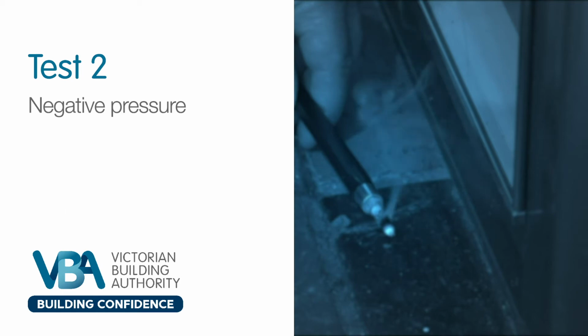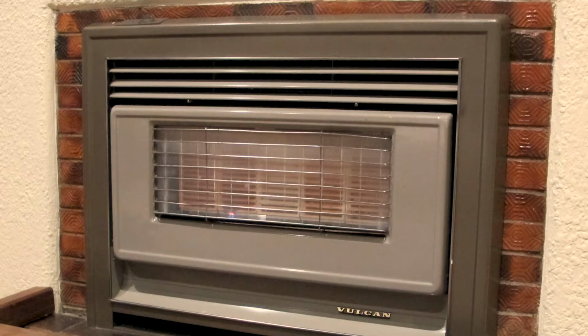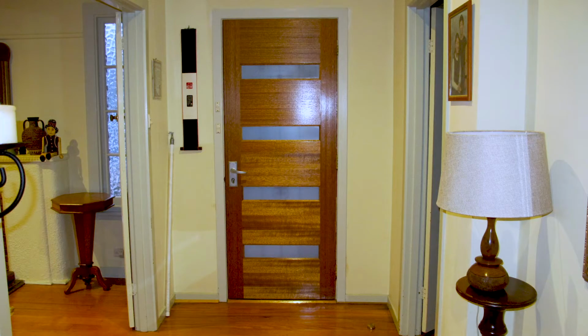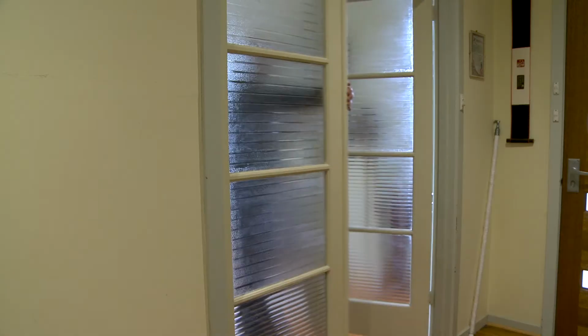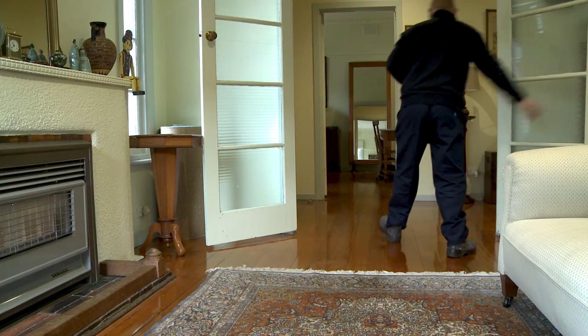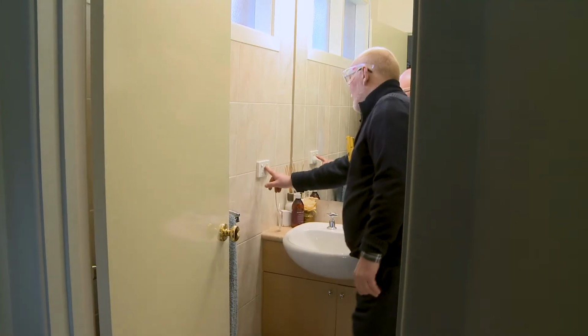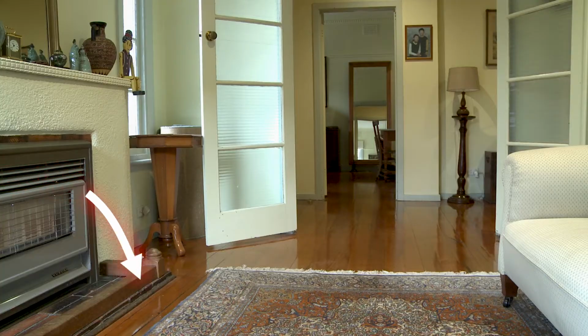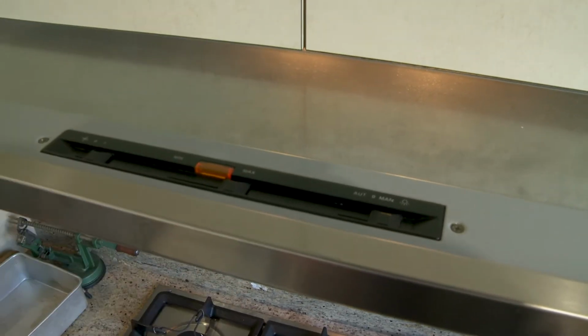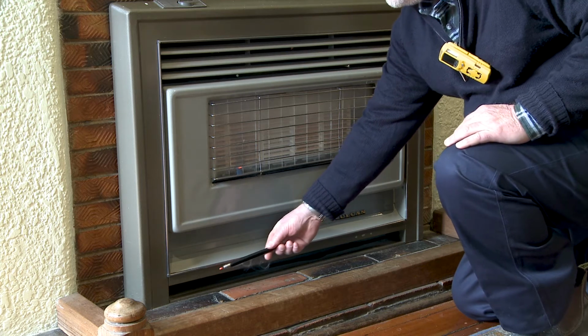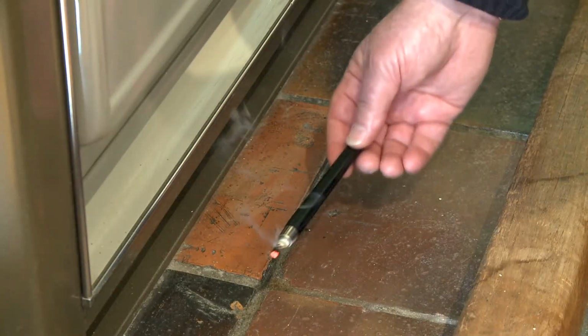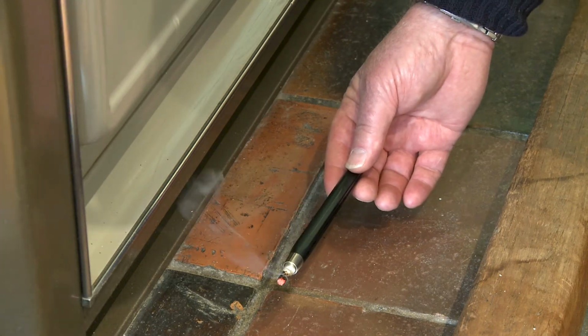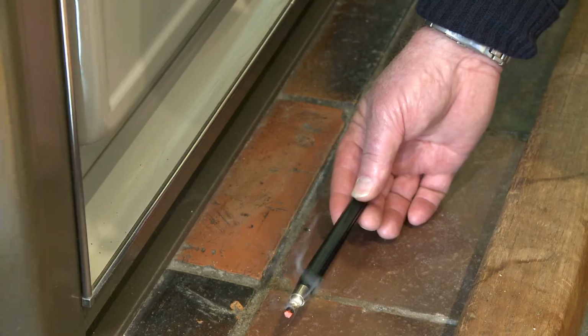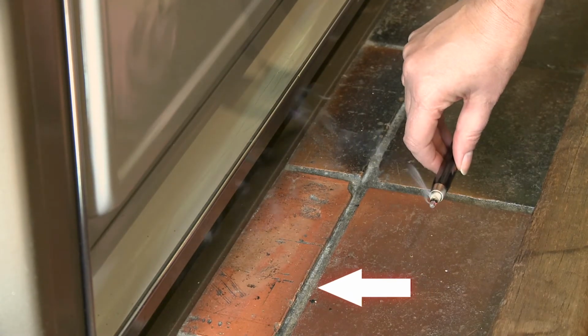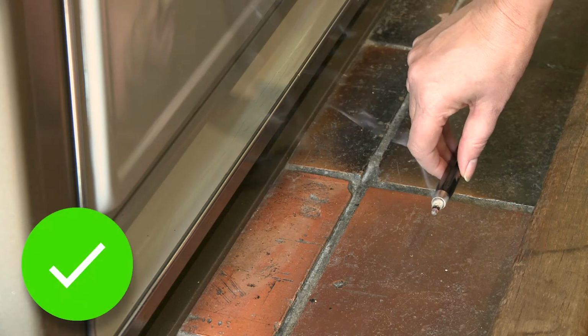Test 2. Negative pressure. Make sure the appliance is not turned on at this stage. First, close all external doors and windows. Then open or close any internal doors that connect the space between the gas appliance and any mechanical extraction fans, including range hoods, to create the greatest negative pressure effect on the appliance. Switch all extraction fans on high before carrying out a smoke test using a suitable smoke-producing device. Holding the smoke at the draft diverter or combustion air intake openings, take note of what is happening to the smoke. If the smoke plume is drawn into the appliance or is streaming straight up, it is safe to move on to the next step.